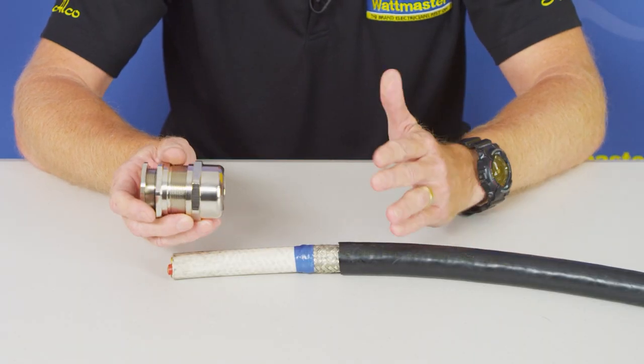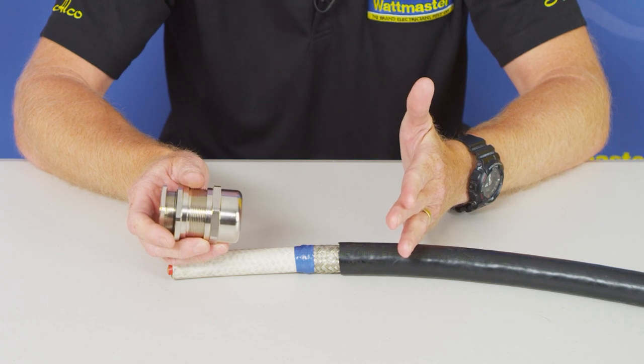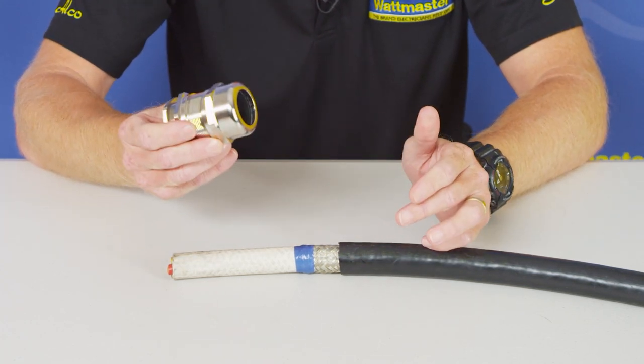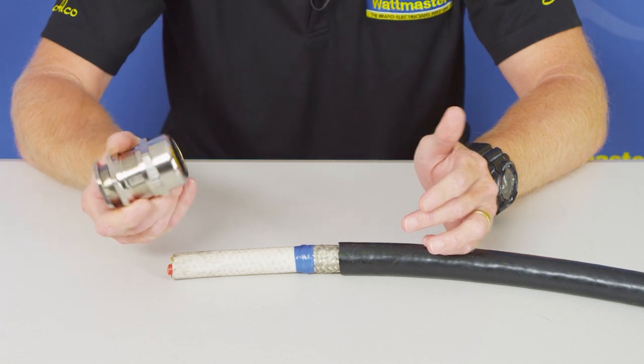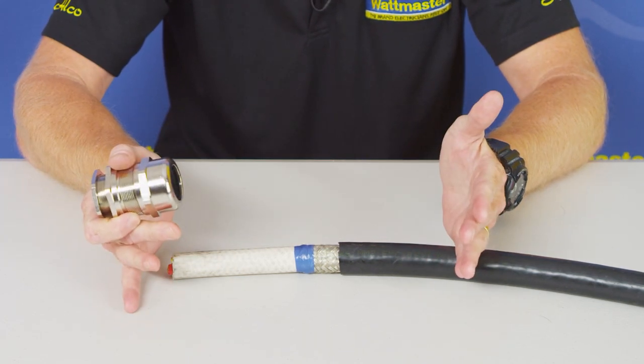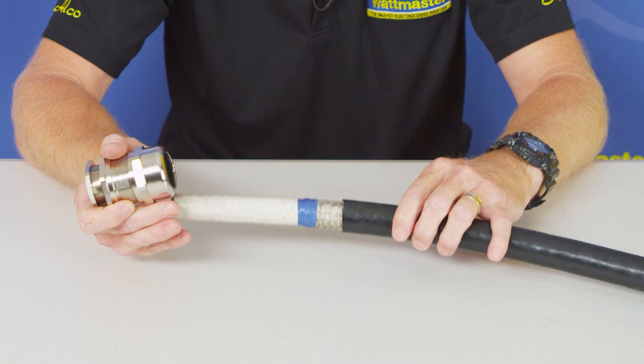So what we have to do, we determine the outside diameter of the cable and the over braid measurement and we make sure our gland fits that cable. Then it's as easy as getting your termination length. We've done it very short here to fit on camera.